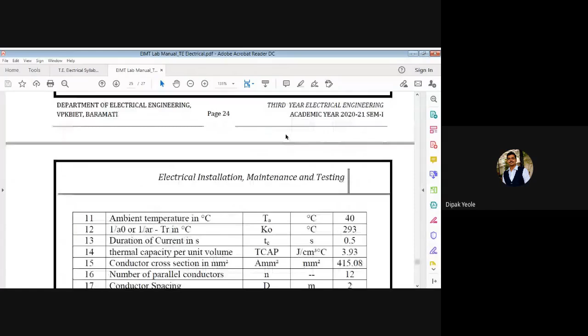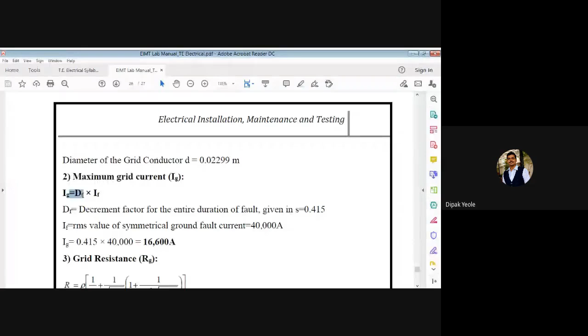Obviously it is in millimeter square, and for this area we have to find the standard size available, which is 23 millimeter. So for the designing of the 220 kilovolt bus section, we have to use 23 millimeter area for this earth conductor. Yes. In the same way we have to develop the second calculation, which is related to the maximum grid current. For the maximum grid current, you have to use the formula Ig is equal to Df into If.